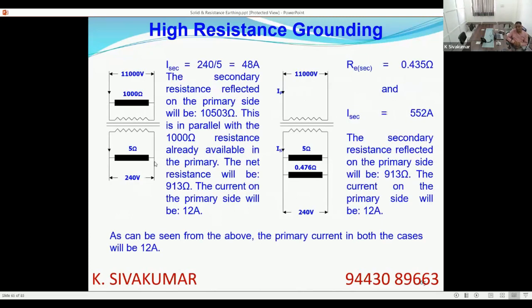I have given some examples. In the first, left hand side example, I am connecting a very high resistance, a 1000 ohm resistance rated for 11 kV. Now the secondary current, if you see, 240 by 5 is 48 ampere. The 5 ohm secondary resistance reflected on the primary side will be approximately 10 kilo ohms, that is multiplied by the square of the turns ratio. This is in parallel with the 1000 ohm resistance, so the net resistance will be 913 ohms on the primary side. The resultant fault current in the primary side will be 12 ampere.